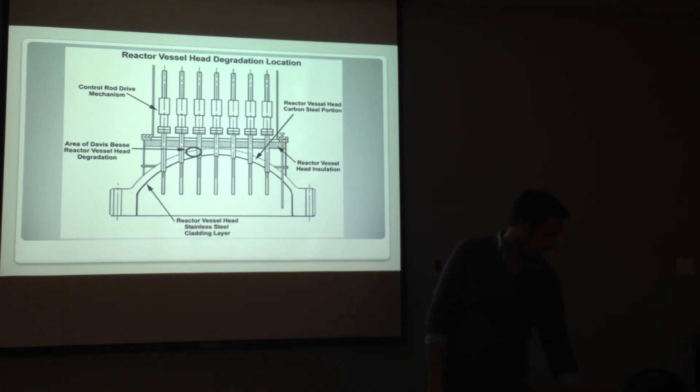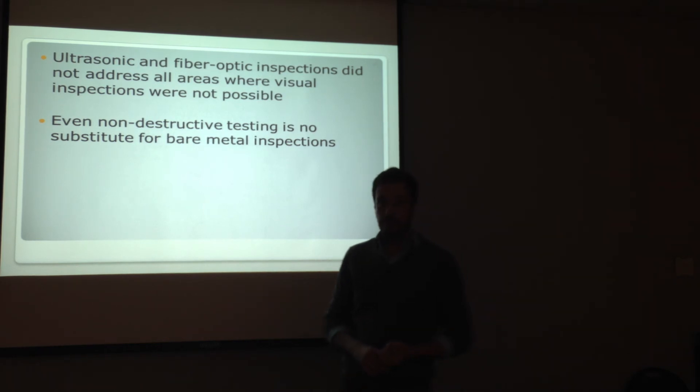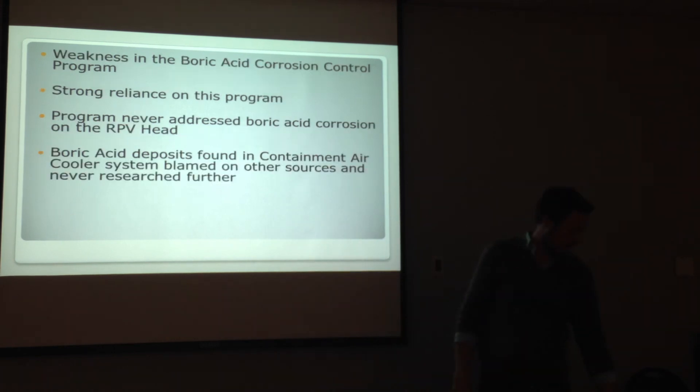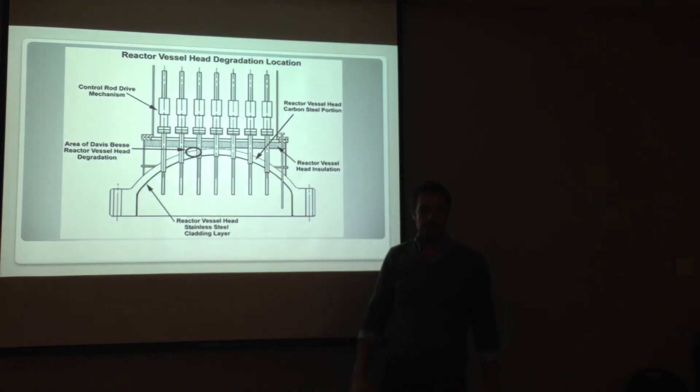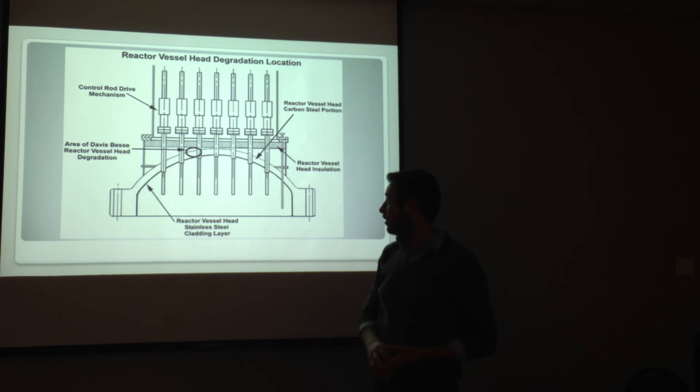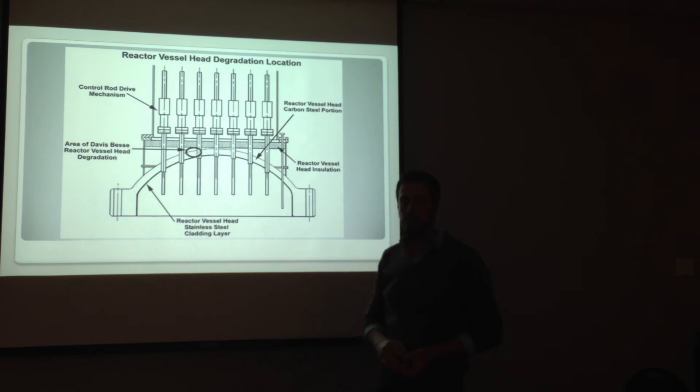And the final thing is that we discovered that there's really no substitute for visual inspections. We call them bare metal inspections. Basically, removing that layer of insulation and inspecting that reactor pressure vessel head. There's no substitute for it. Ultrasonic testing, if it would have been done farther down, would have helped. And would have aided in discovering this incident a lot sooner, possibly. But, there's really no substitute for actually inspecting that area there.